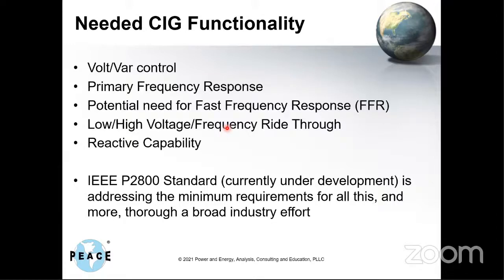There's a standard right now, currently under development, called IEEE Standard P2800. It's a draft, and it's gone through one set of balloting, and right now they're addressing the comments to put it out again. Jens Bomer from EPRI is the chair. That standard is making the first industry-wide attempt to set minimum performance requirements for all these kinds of functionalities and much more, so there's some minimum standard by which this equipment is designed, available, and has capability, so that as it goes into the grid it can do the things we need it to do.